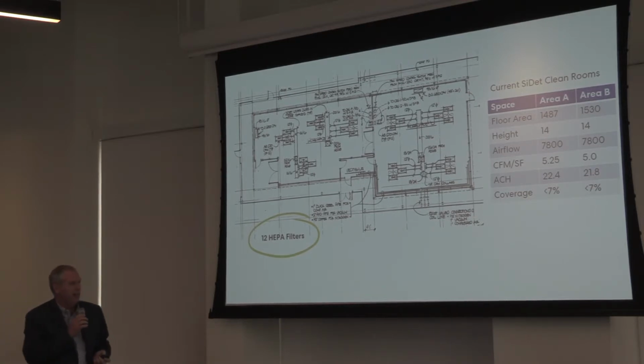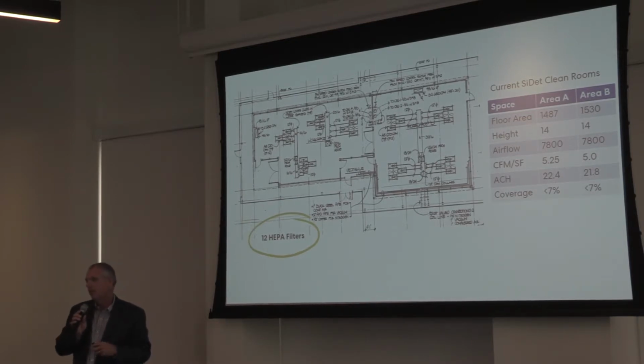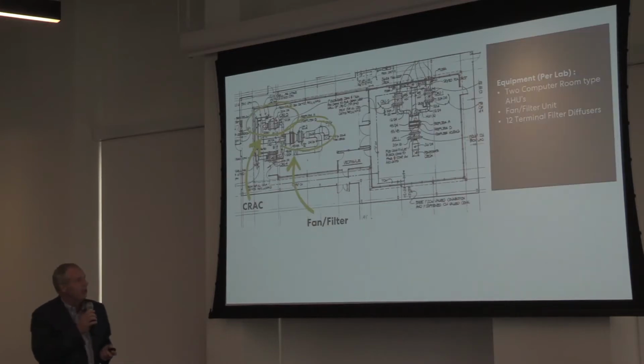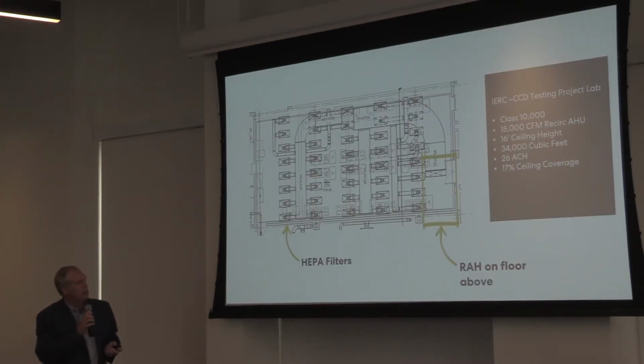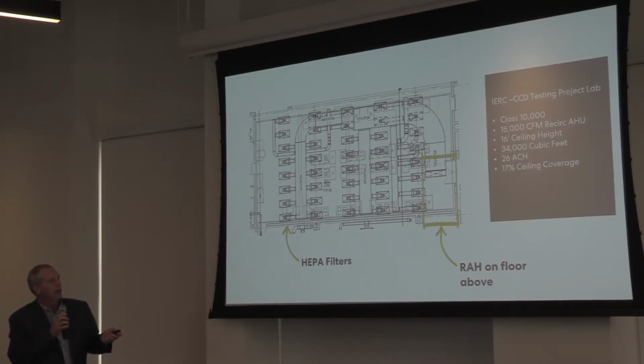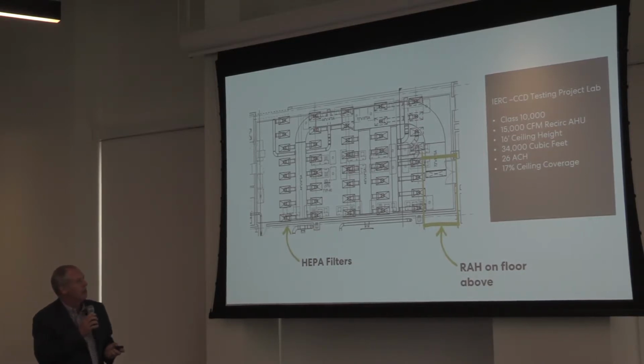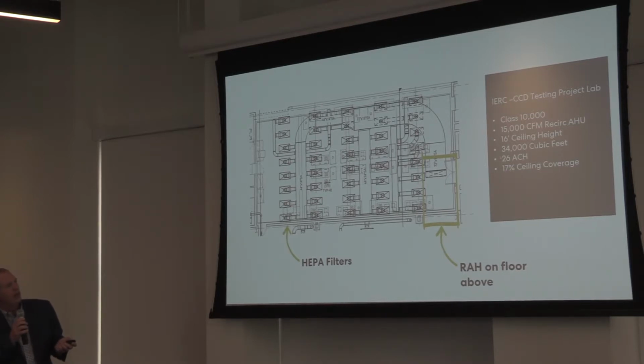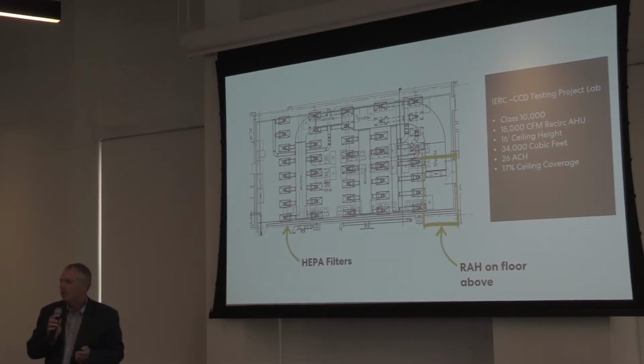Where we're currently at in the design, as Dana mentioned, we're not completed yet, so this isn't the presentation where we say these are all the great things we did. We're still in process here. But we've got a concept which somewhat mimics what they've got out there. We've got a recirculating air handling unit on the mezzanine above, boxed in here, a number of HEPA filter units in the ceiling, and we're at about 26 air changes per hour, closely matching what they've got in their existing lab for that high volume space. We are looking at higher ceiling coverage on the clean room HEPA filters at this point.